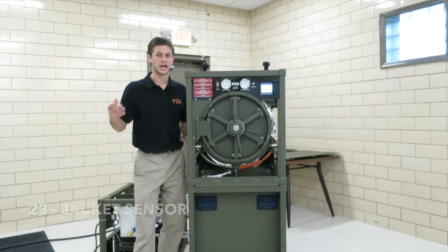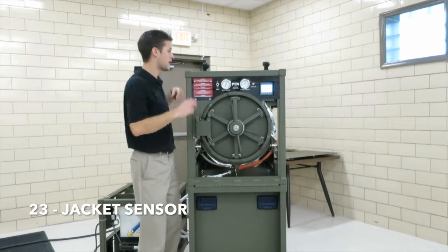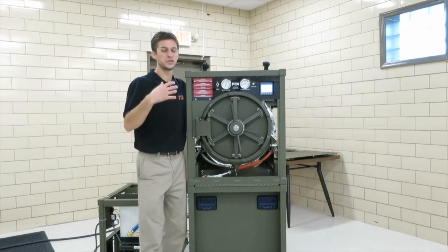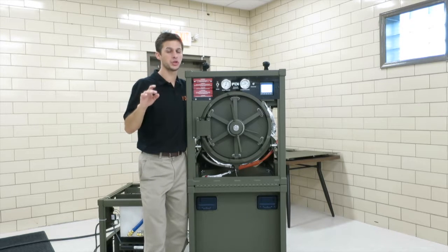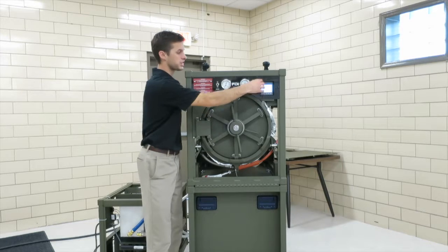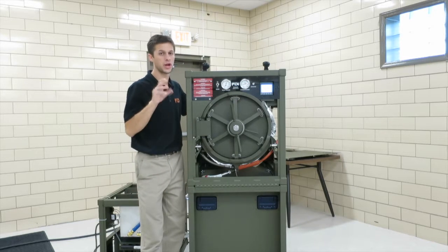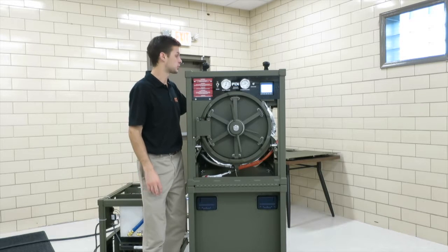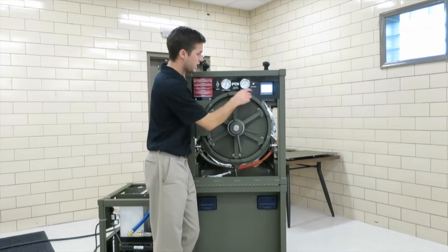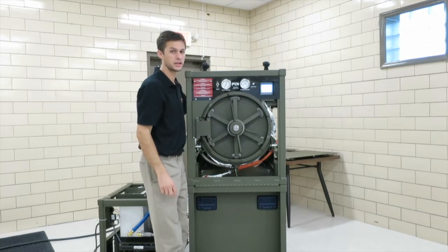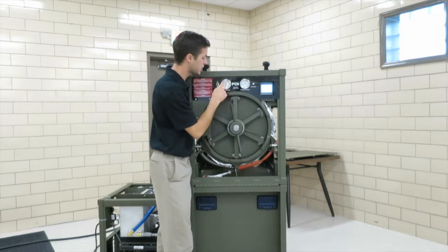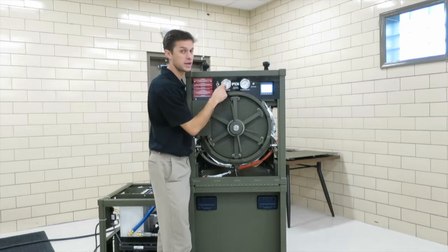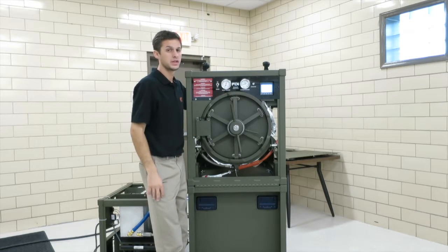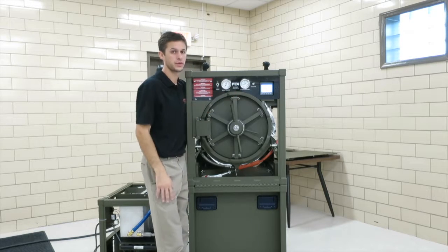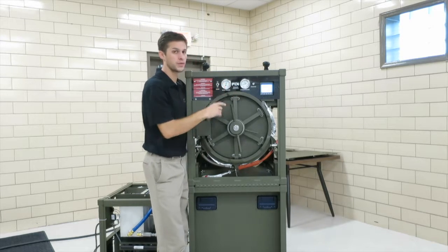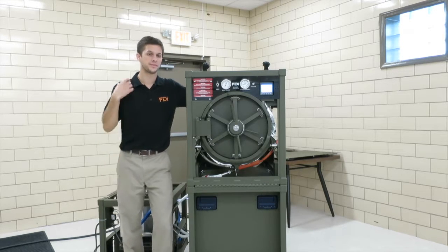So number 23, the last alarm, is the jacket sensor alarm. This alarm is just for if it loses signal, because we've already covered the jacket high pressure alarm. But if the PLC notices that the jacket sensor is no longer outputting a signal, say the cable got damaged or the transmitter got damaged during transport, if the PLC is not receiving a signal from the jacket pressure transmitter, then it can't control at its 28.5 psi idle, and so it'll throw this alarm so that it doesn't overpressure with the heaters. So it's a very important alarm when you're just sitting at idle, the number 23 jacket sensor.